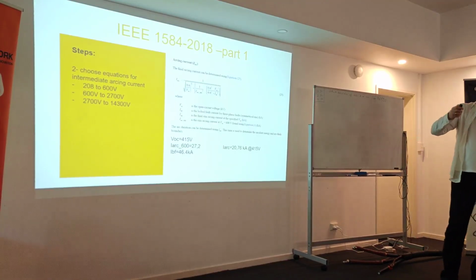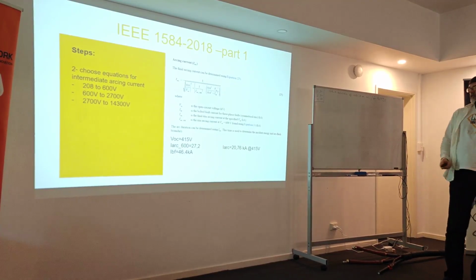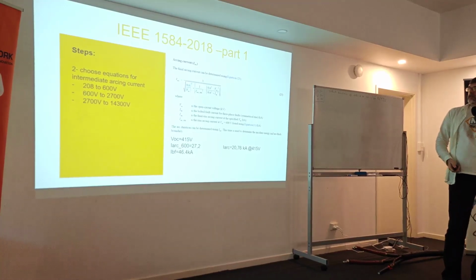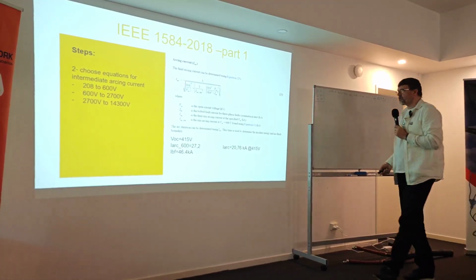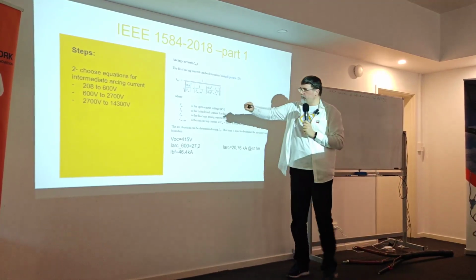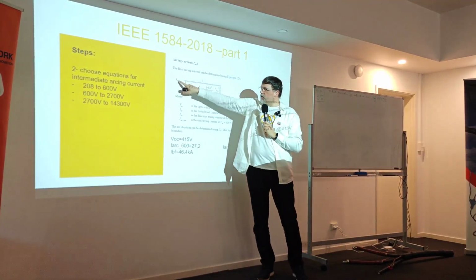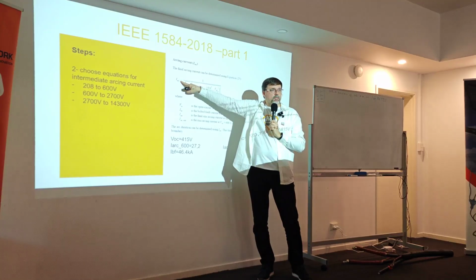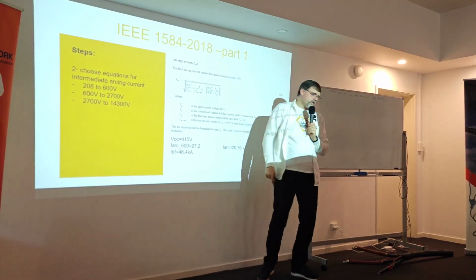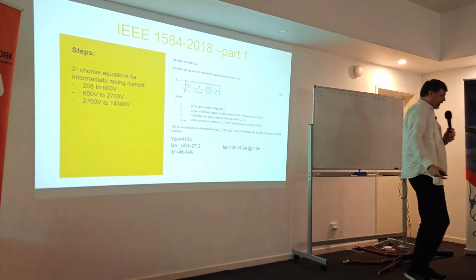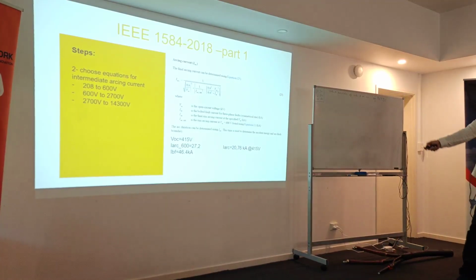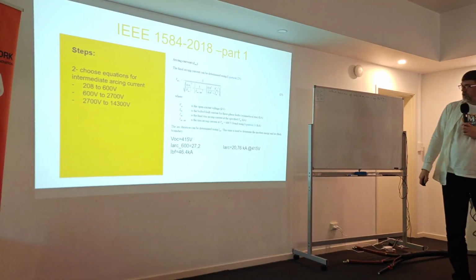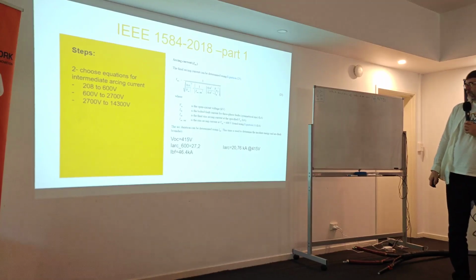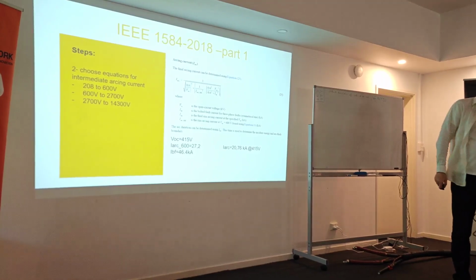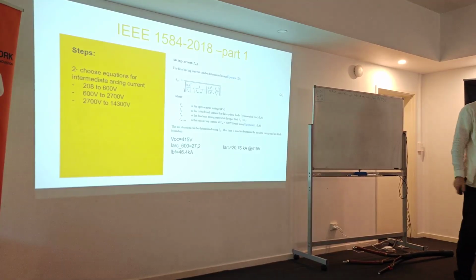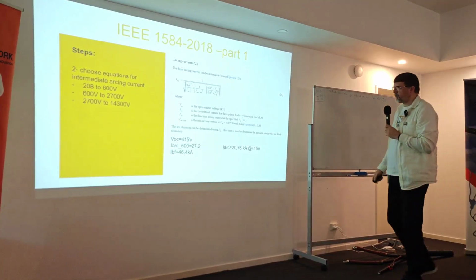But there is a second thing we have to calculate now. So now we have to calculate the final arcing current, which is based on the specific voltage, because the equation was for the 600 volts. So now I have to recalculate it for the 415 volts. So that's what I did. So we find out the final current is 20.7. So yeah, good to go, yeah? So it's less than 50%.